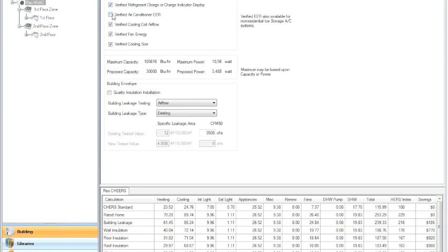So when you install that air conditioner, you're going to make sure that the refrigerant charge is correct. So there's all these upgrades that you can make to the air conditioning system that represent the benefit from either properly sizing it, properly sizing the airflow across the cooling coil, properly selecting the fan, and an ECM fan motor would be appropriate here, and even the selection of the EER. If you've selected an air conditioner that has a better EER on it than normal, so maybe you've got a 13-SEER air conditioner with a 12 EER. Okay, so there you could say, okay, I've got a better EER. So these would be all upgrades that you can consider.